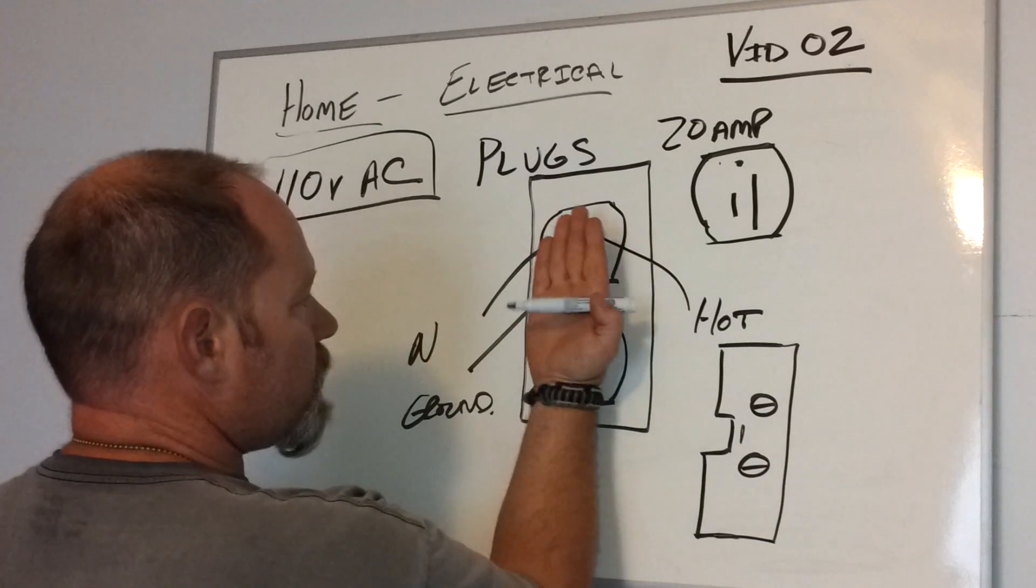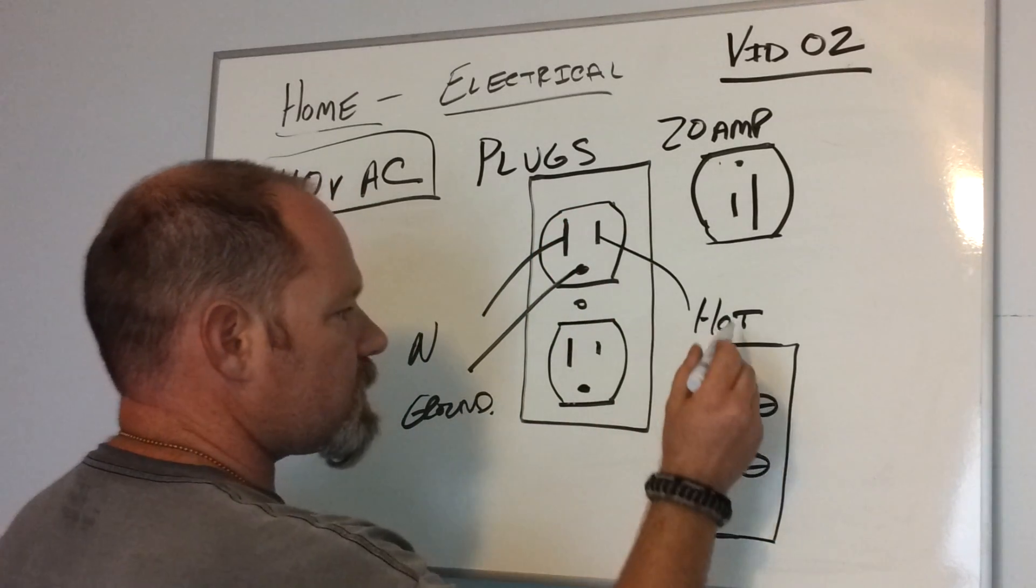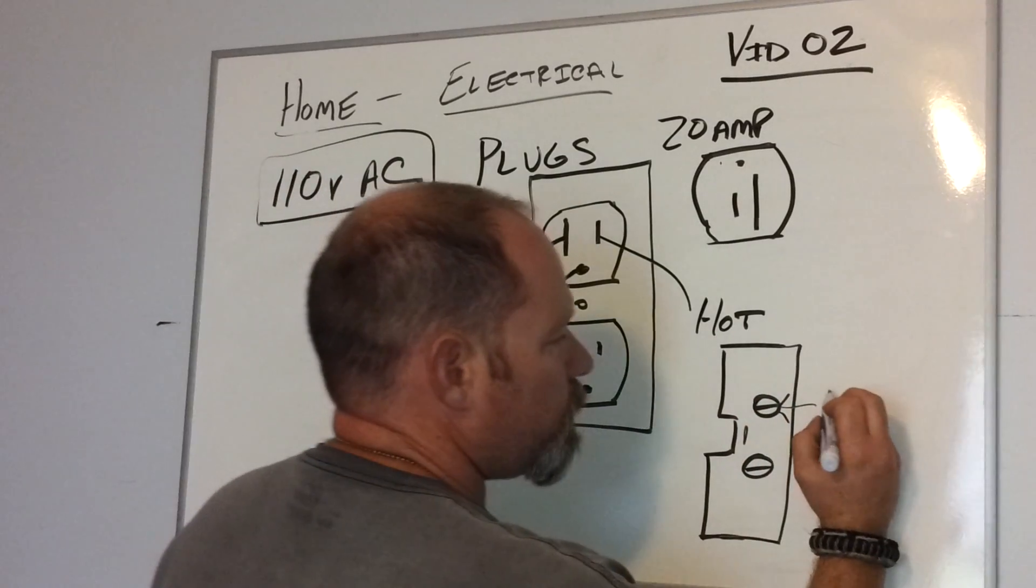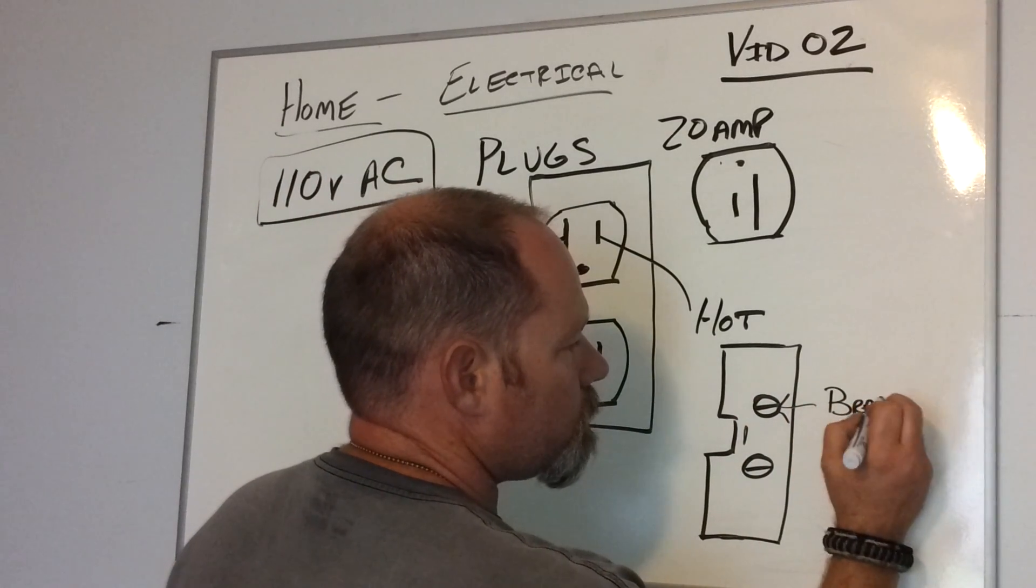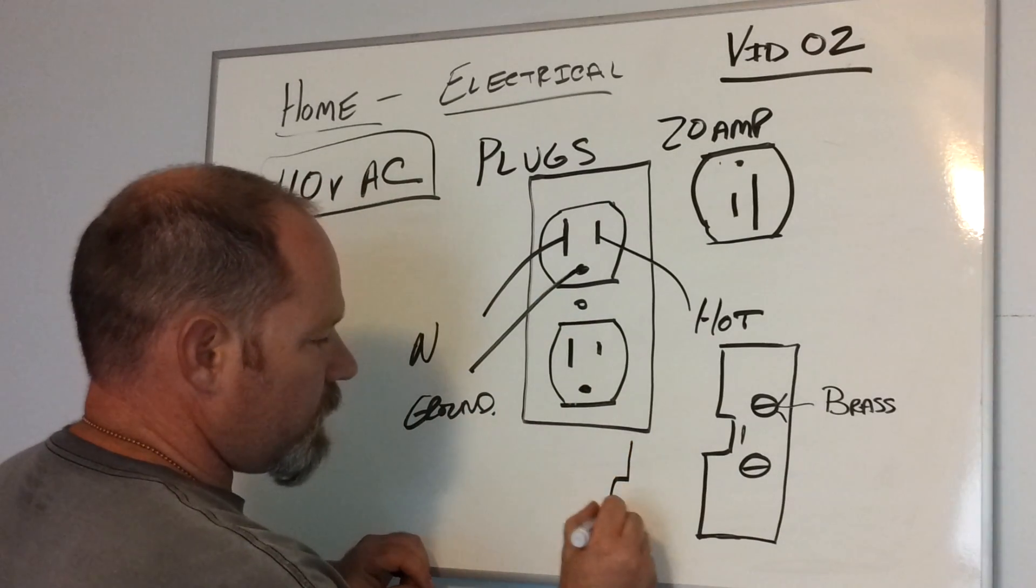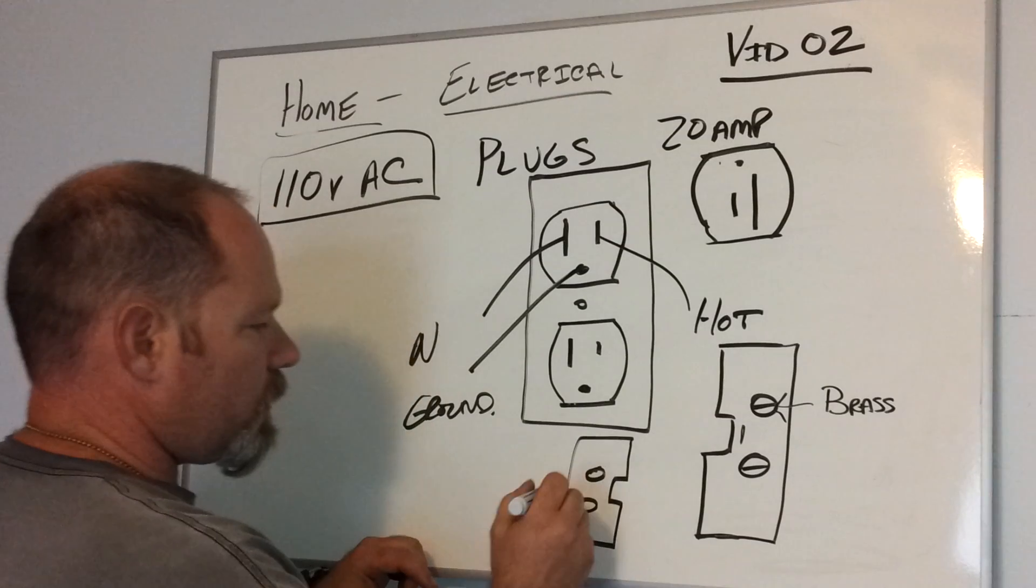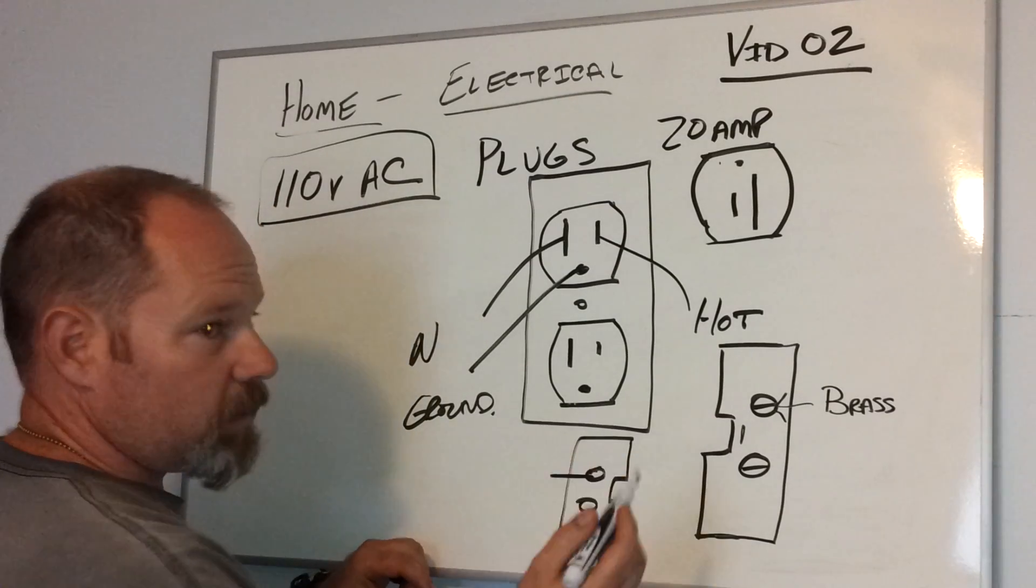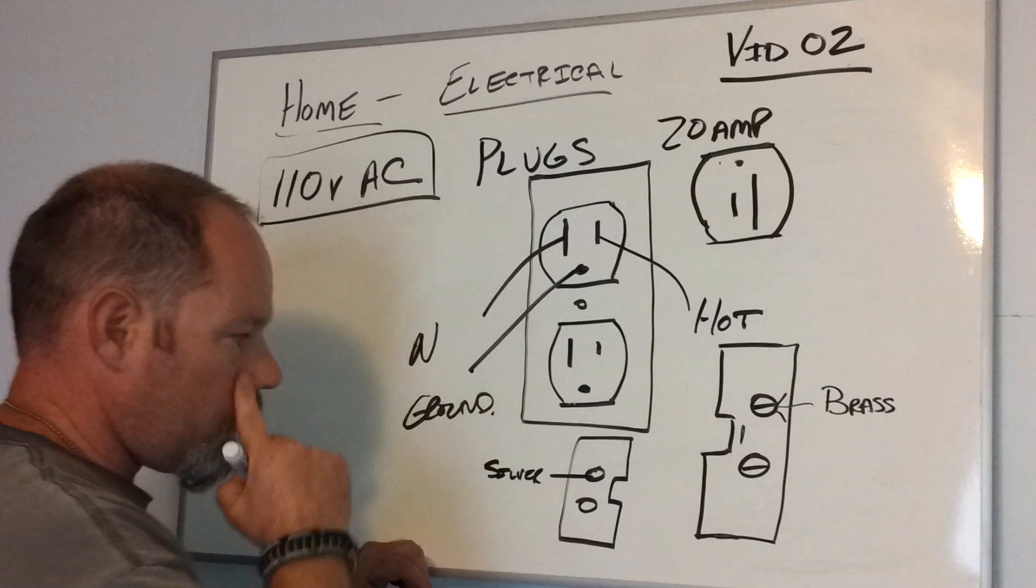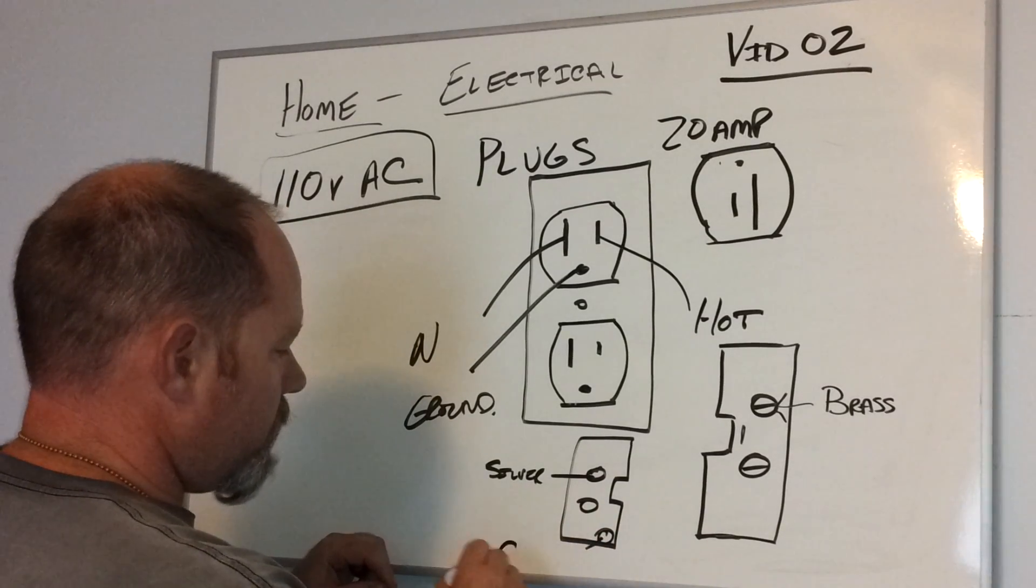By looking at this, we've taken this plug and turned it sideways. Now, we know that this is the hot side, so there's a color coding on these—and it's brass. If you flipped it the other way, you see the two screws. They're going to be silver or nickel. Your ground terminal is typically going to be down here, and it's going to be green.